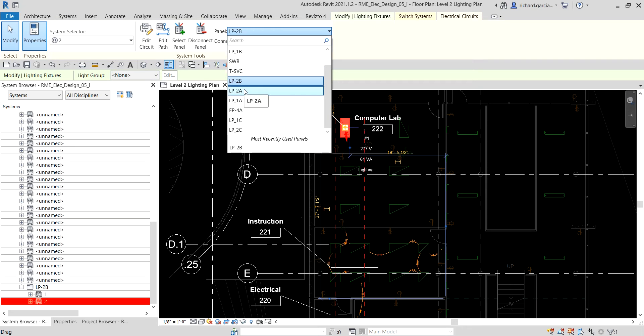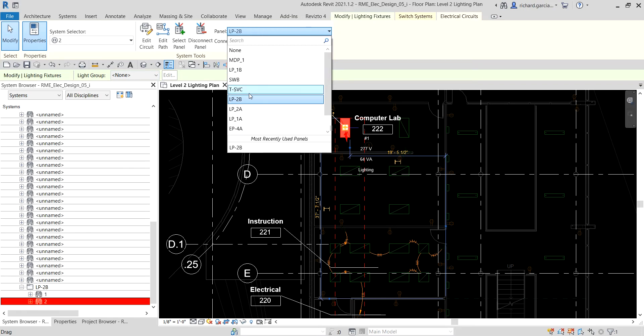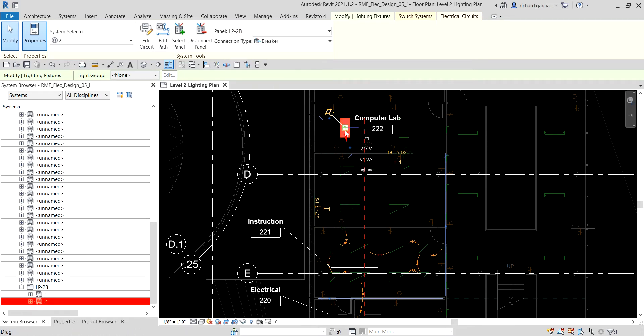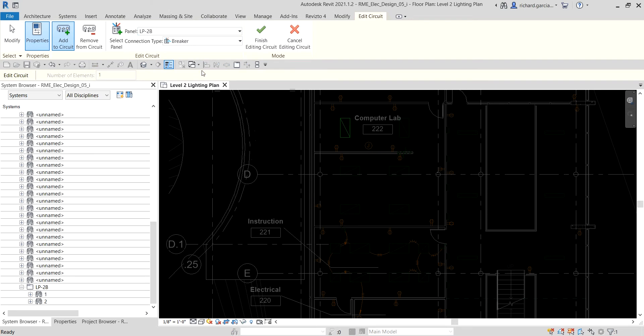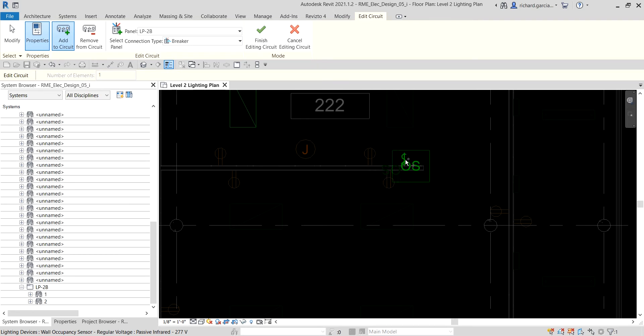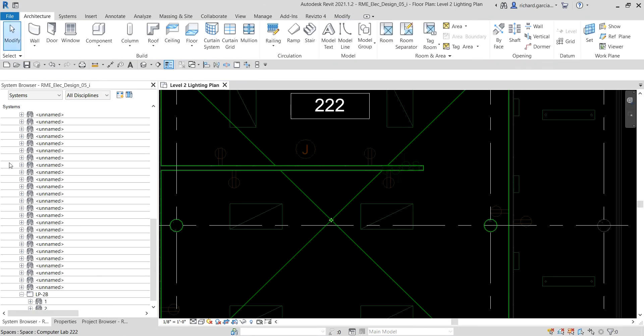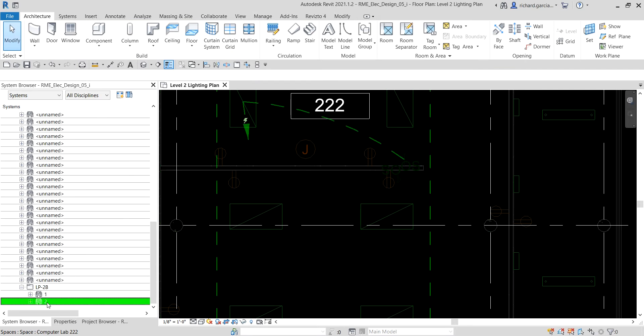From Electrical Circuits you can select the panel you want to assign — LP2B, or Electrical Power 4A, or any other available panel. For now I want LP2B for that particular lighting fixture. I'll select Edit Circuit because I want to add the occupancy sensor to the circuit, so I select it and it gets added. Then I select Finish Editing Circuit.